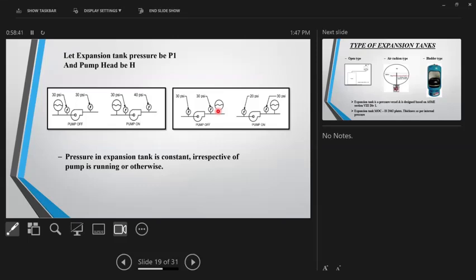Okay, we were also talking about reference pressure. What does that mean? Again, these are two figures taken from ISHRAE. Imagine the pump is off, and the expansion tank is, let's say, at the pump inlet. Obviously, you will see what the static head is. Let's say 30 psi. Pump is not running, so pressure is the same.